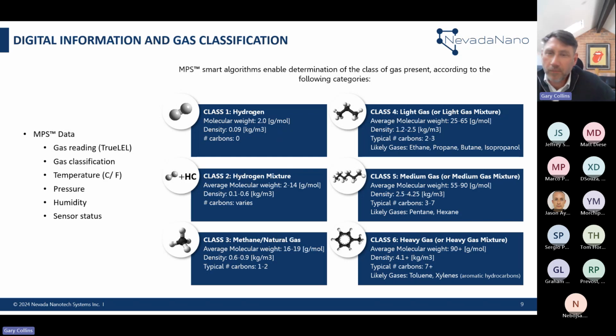This is a really important piece: if you use a digital sensor, you can make it effectively filter out other combustibles. Many people might use the chem equivalent, which has side effects with cross interference of other gases. So this is one way, using gas classification, to guarantee the sensor will not react to other gases.